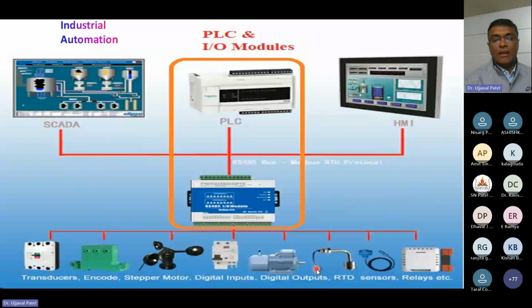These voltage signals are applied to the IO module, which converts the analog value into a digital value, and that digital value is applied to the PLC. In the PLC, we read that digital value and write a program to turn on the AC whenever the temperature is greater than 25 degrees centigrade.